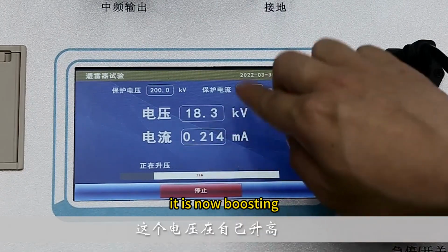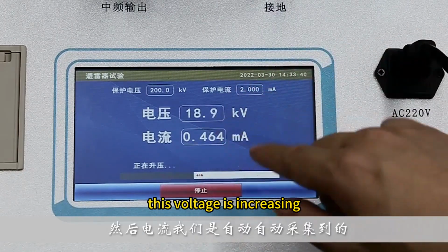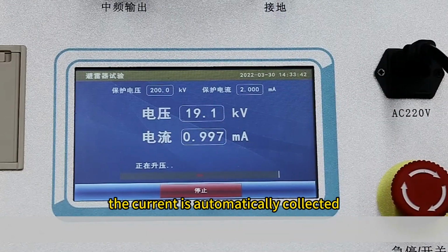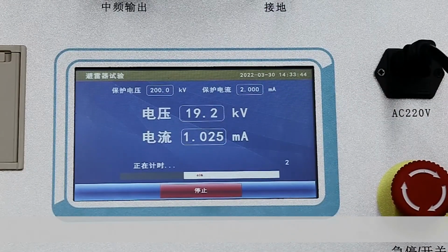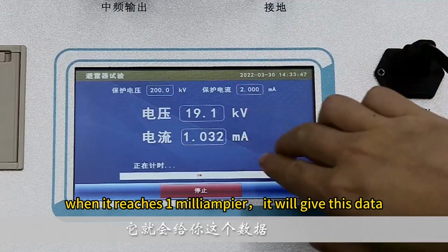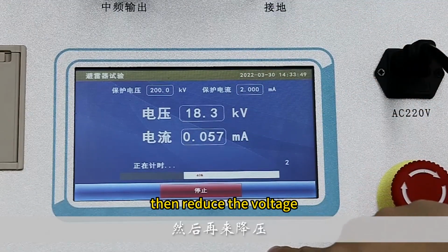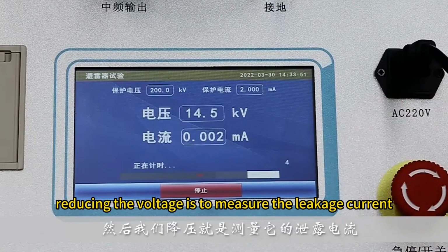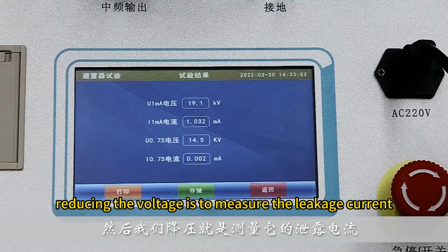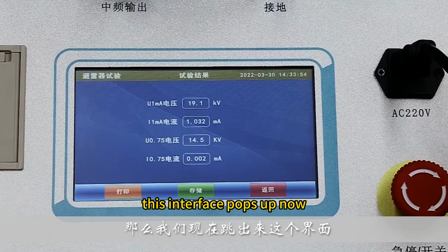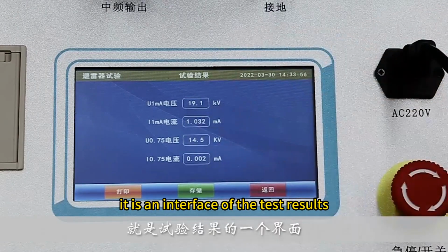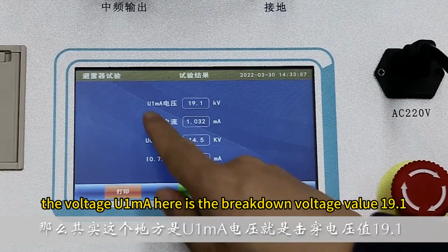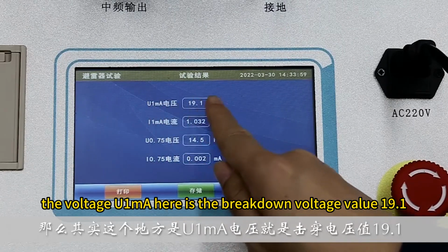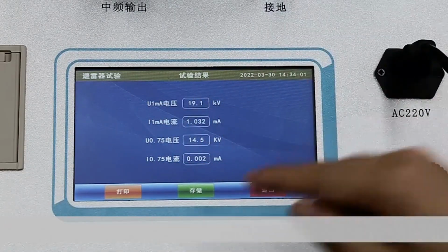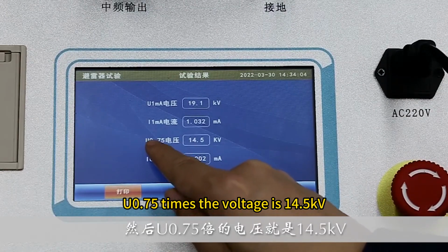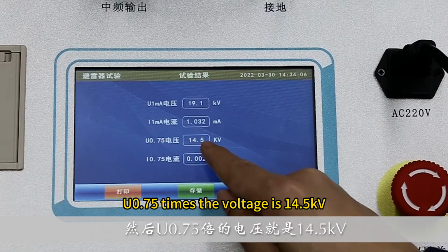It is now boosting. This voltage is increasing. The current is automatically collected. When it reaches 1 mA, it will give this data. Then it reduces the voltage. Reducing the voltage is to measure the leakage current. This interface pops up now. It is an interface of the test results. The voltage U1mA here is the breakdown voltage value, 19.1. U0.75 times the voltage is 14.5 kV.